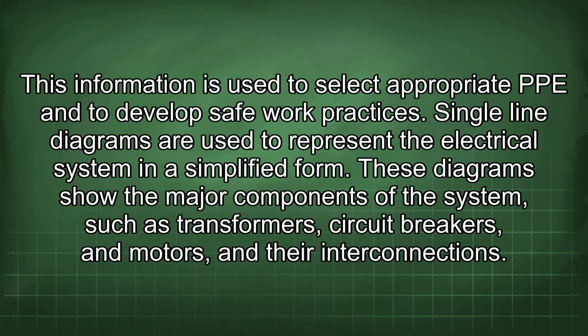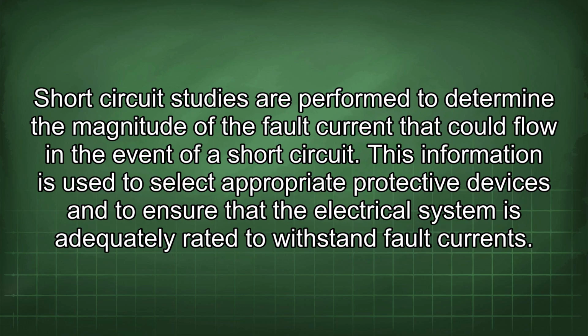Single line diagrams are used to represent the electrical system in a simplified form. These diagrams show the major components of the system, such as transformers, circuit breakers, and motors, and their interconnections. Short circuit studies are performed to determine the magnitude of the fault current that could flow in the event of a short circuit. This information is used to select appropriate protective devices and to ensure that the electrical system is adequately rated to withstand fault currents.